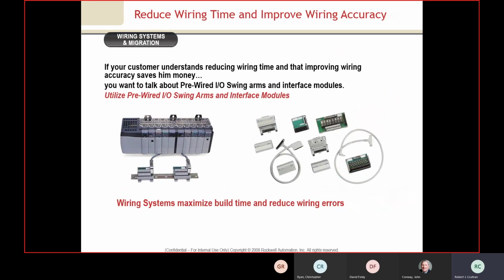This wiring system is a very unique product, and it fits a couple of categories. One is a situation where you've got a lot of cabinets to build. This allows you to wire incoming to one side of this terminal block, and there's a connector cable that snaps onto the I/O module. You'll notice several different types of these terminal block connector units - they have surge protection in them, and you can buy them with fuses, in all different types.